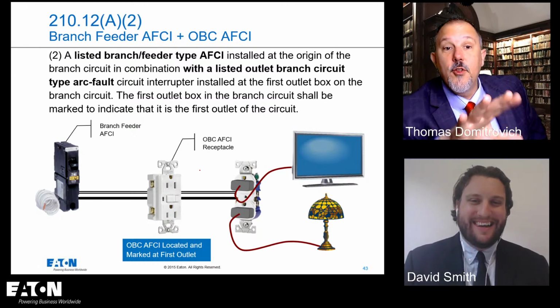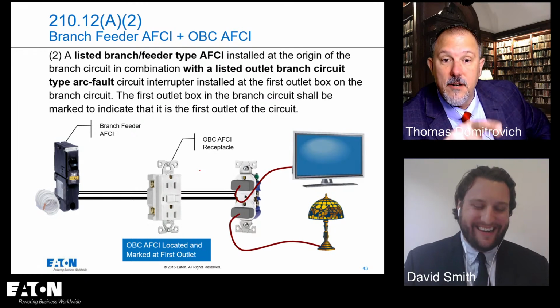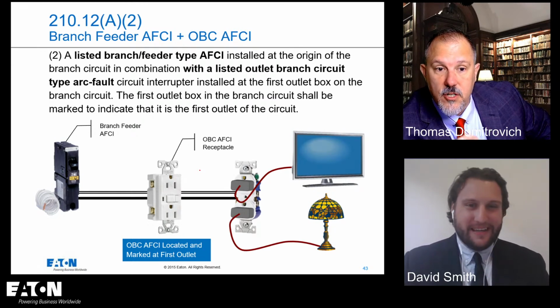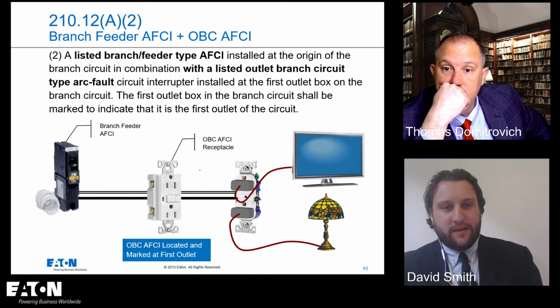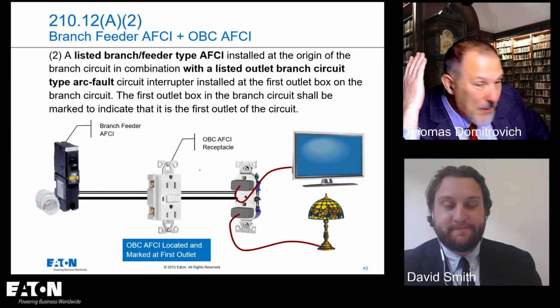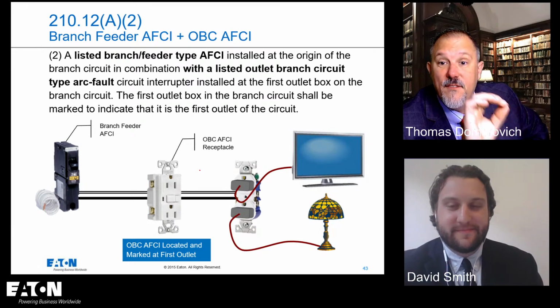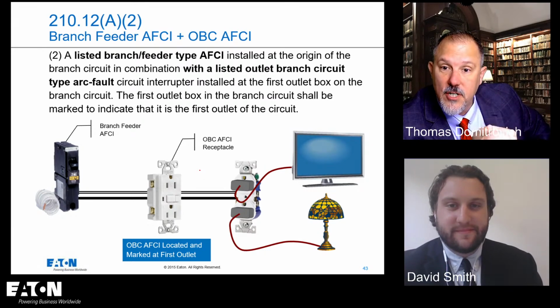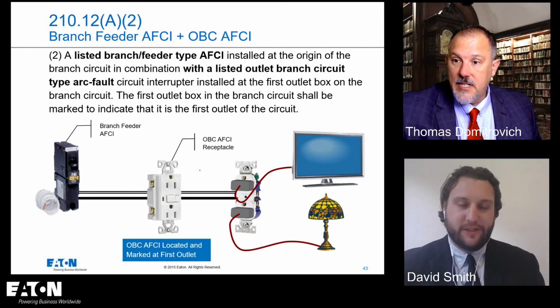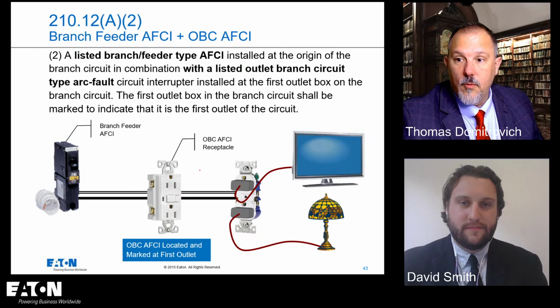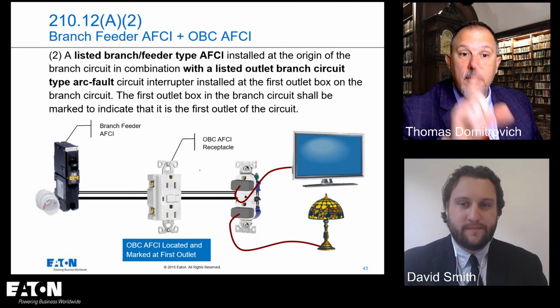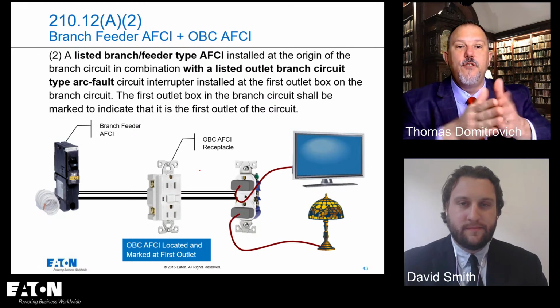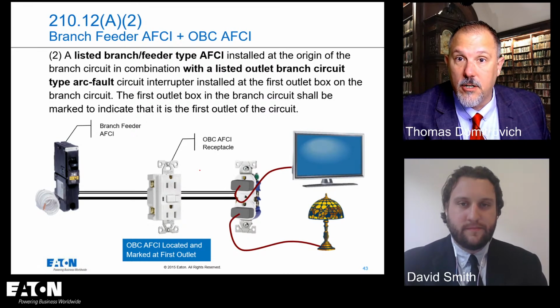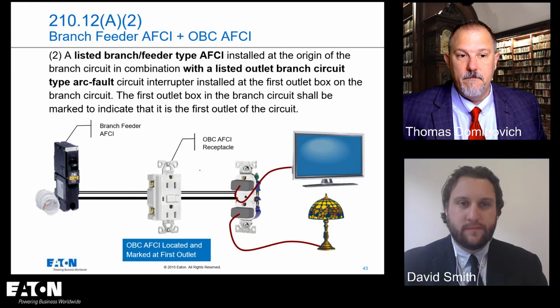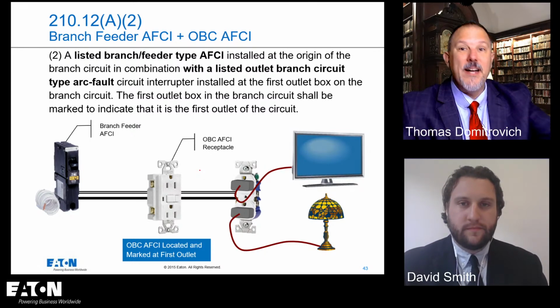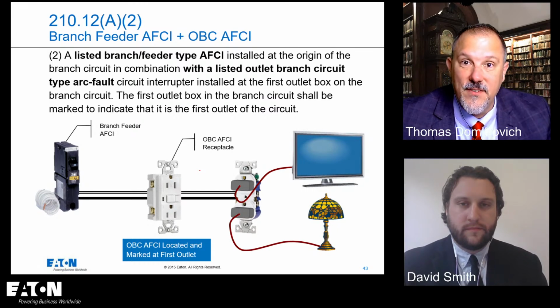So this one here, the reason, David, why is there no distance, no length of this OBC? Why isn't it 50 or 75 feet? I don't know, Tom. Why is it? Because the branch feeder AFCI provides the parallel arc and series arc protection for the NM wire. You're protecting that home run circuit from arc fault. So the OBC doesn't have to; you have no vulnerability with regard to series arc or parallel arc of the home run circuit. All right. So no distance, but here's the challenge. Try to find a branch feeder AFCI.